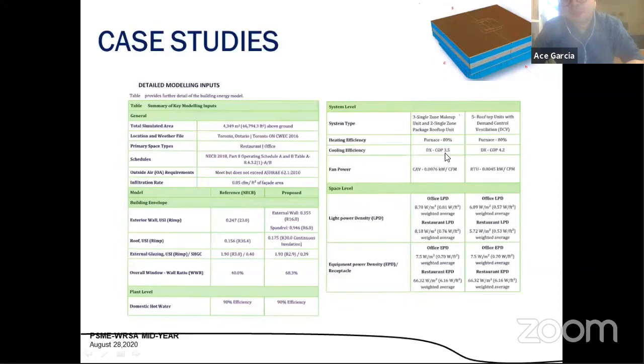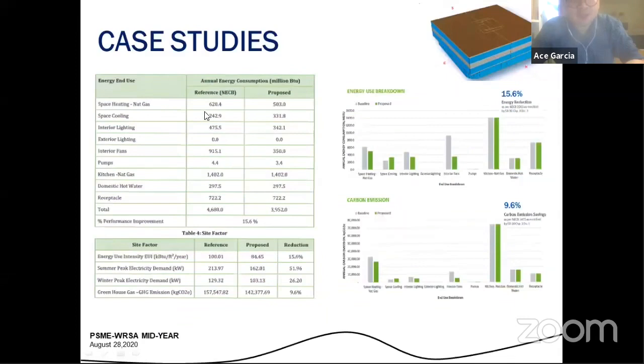They have specific performance requirements in the building: for cooling, it should have a 3.5 COP, the furnace should be 80% efficient, and lighting power consumption and fan power are based on airflow divided by power - that's the fan power limitation we have. All of these building characteristics in our proposed design should be equal to or better than baseline for us to know whether the building complies for permit. So when we run this information in our energy model, we see a huge reduction in energy.